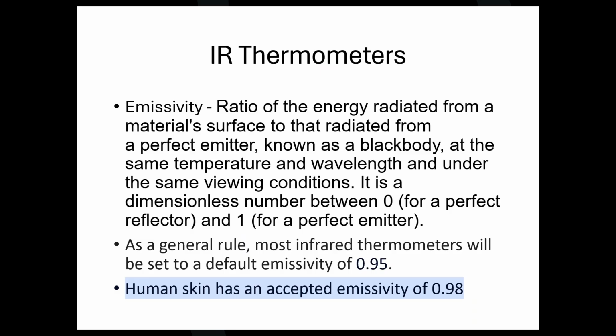So we have basically 0 to 1 on this scale. Human skin has an emissivity of 0.98. I think that's kind of unique, 98 degrees, 0.98. The ones you buy at Lowe's hardware are 0.95. That throws everything off. If you're measuring, let's say, a sterilizer, I've seen people do it, measuring the heat bands going around the autoclave. Very shiny, isn't it? You need something with an emissivity lower than even that 0.95.